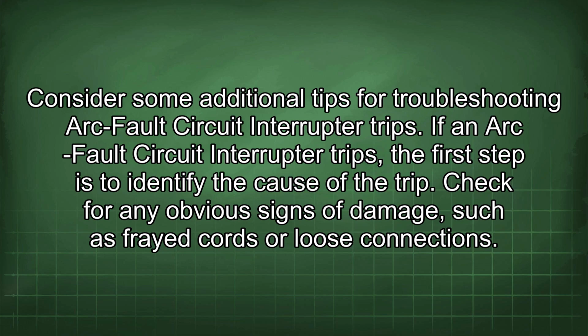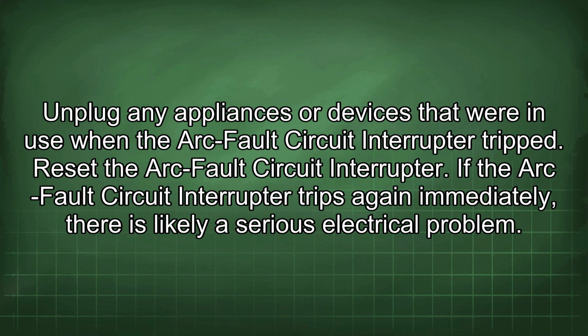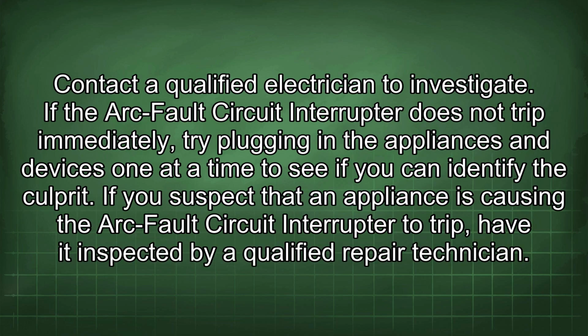Consider some additional tips for troubleshooting arc fault circuit interrupter trips. If an arc fault circuit interrupter trips, the first step is to identify the cause of the trip. Check for any obvious signs of damage, such as frayed cords or loose connections. Unplug any appliances or devices that were in use when the arc fault circuit interrupter tripped. Reset the arc fault circuit interrupter. If the arc fault circuit interrupter trips again immediately, there is likely a serious electrical problem. Contact a qualified electrician to investigate.